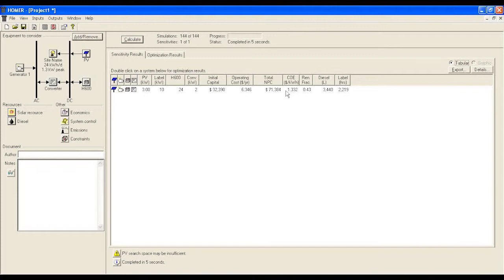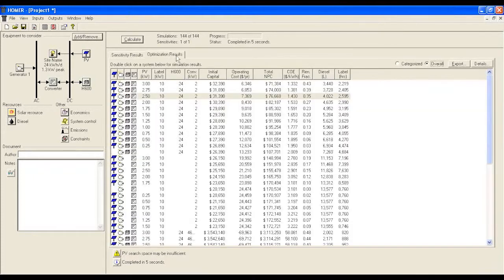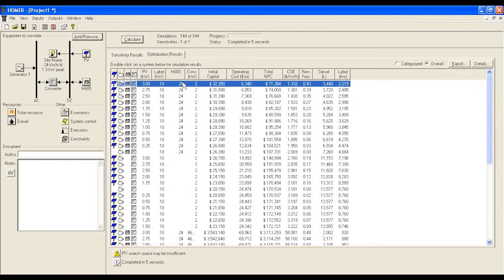For a DG hybrid solution, our recommended DG run hour is a maximum of 3 hours per day. On the other hand, if you want to go for a pure green source, you have to look for a solution where DG is not recommended and the DG run hour shows zero.